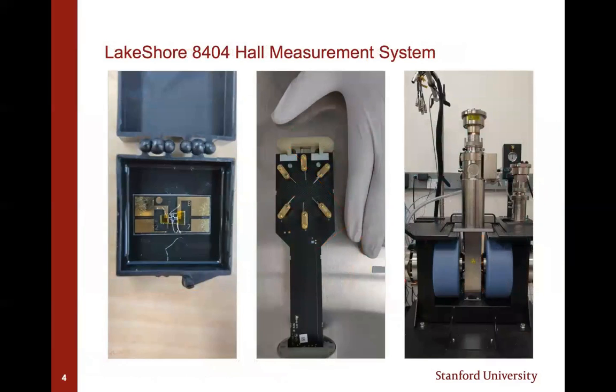Now, to test these individual sensors, independent of the STB, we used the LakeShore 8404 Hall measurement system, capable of a wide range of temperatures and fields over 1.5 Tesla. Here's our die, which is taped onto this small pad and then pinned here. Now, this is mounted down between these 2 very large magnets, the big blue cylinders here. While of course the LakeShore cannot simulate a transformer, it was able to tell us how these sensors themselves would perform under thermal and high magnetic field stresses.